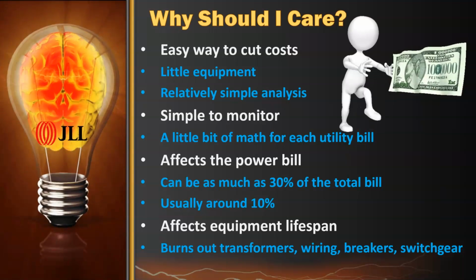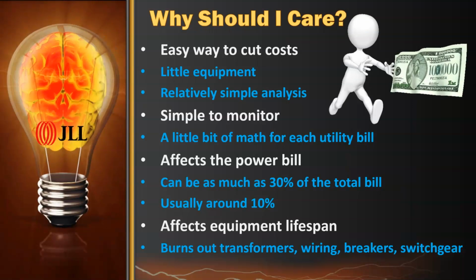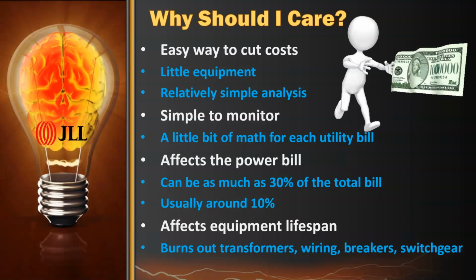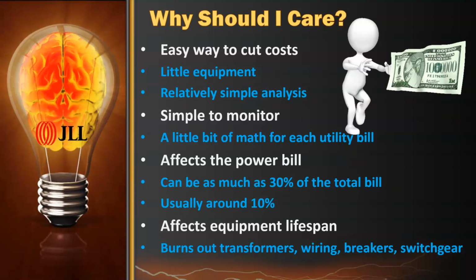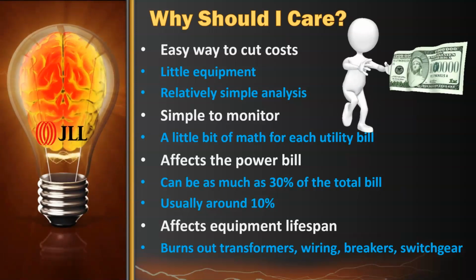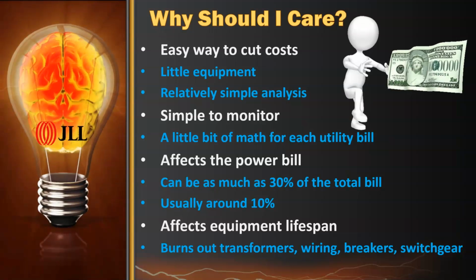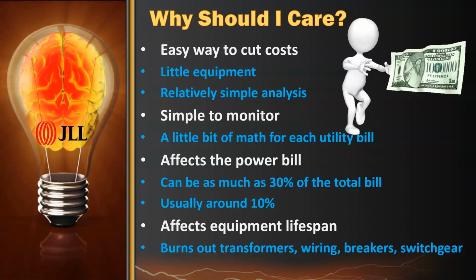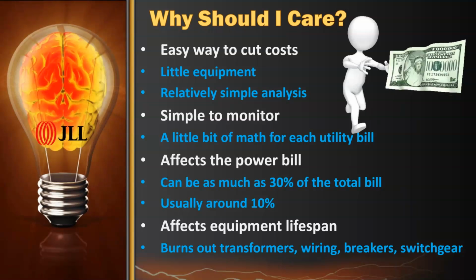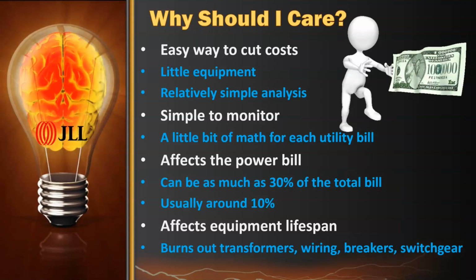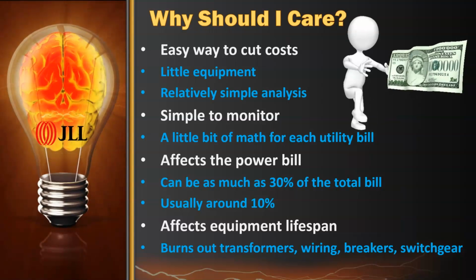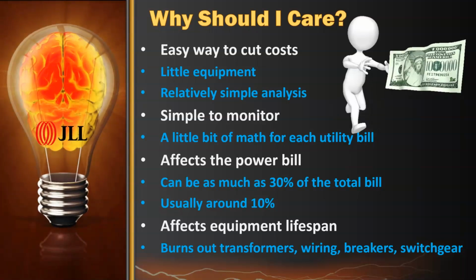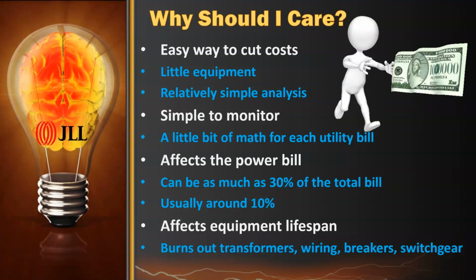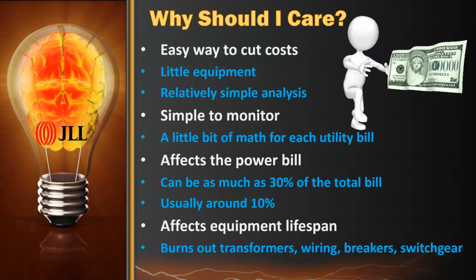It does affect equipment lifespan. Harmonic and transient energy will burn out transformers quickly. Typically you might get 20 or 25 years out of a transformer. If you have a pretty high harmonic load in the 30% range, you might only get 5 to 7 years out of that transformer, maybe even less. It'll cause nuisance breaker trips, it'll cause issues with wiring, and can burn out the grounding grid. It might cause problems with X-ray and radiology equipment, and with elevators. So harmonics are a problem.